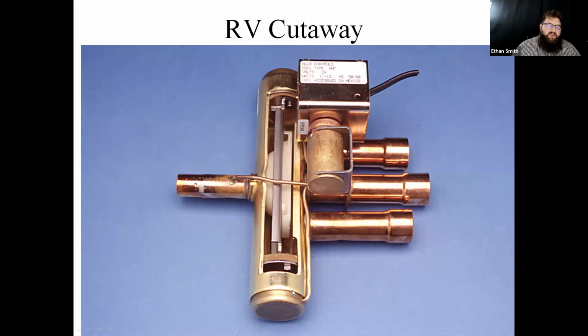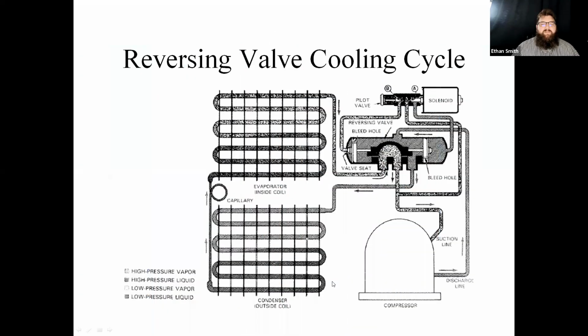There's a picture of an actual one. You can see the seals on either side, little bleed holes, and we've got our Teflon clamshell that slides back and forth on top of the valve seat right here. And then we've got our pilot valve, our little capillary tubes that go to either side, and then our suction, discharge, and our 2 coil lines.